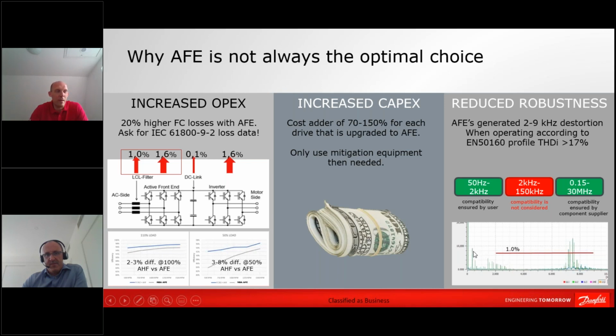If you look at your power supply, there might be a drive that has a resonance point, let's say at 8 kilohertz. And now you have something that is injecting current at 8 kilohertz. And that means that you have a hammer that hits on this 8 kilohertz. And the noise of the bell depends on how hard you hit. So the bigger the peak becomes, you might not have a problem with 8, but you will definitely have a problem if you're hitting very hard with a hammer. So the peak here is the strength of how hard you hit with your hammer.